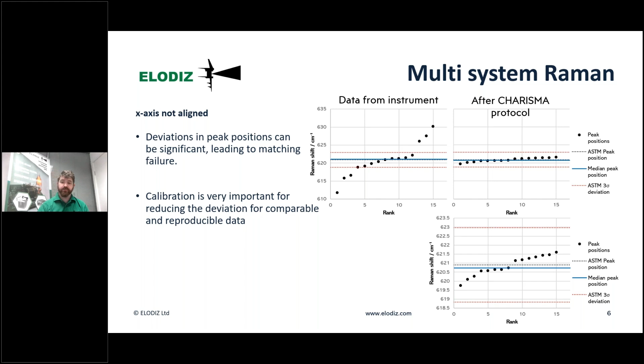So again, to expand on that, another way that people look at data, instead of performing things like peak fitting, is they will perform correlation scores, so things like HQI or Pearson R's, to look at how closely related two different sets of data are. So I'm looking at these two systems here, and as you can see, it has a correlation score of about 92%. Now, 92% doesn't seem particularly bad, but a lot of thresholds use something like 95% in different industries based on different standards. So these would actually say that these are not the same material, even though I'm well aware that they are exactly the same sample taken on two different systems.